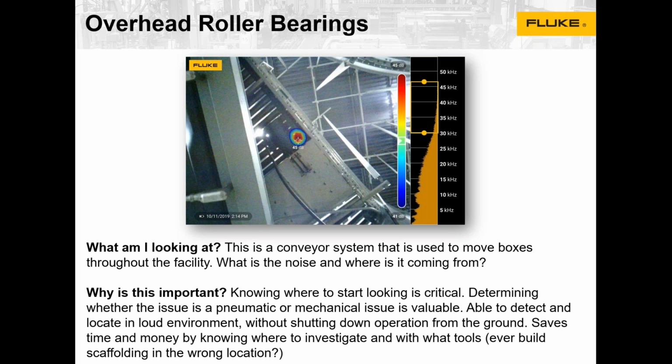And in this case, what we're looking at is actually noise from the bearing, but it could be a pneumatic leak as well. Being able to pinpoint that from the ground quickly can reduce your time and money in really getting up there and fixing it, bringing the right tools, even whether you're going to build scaffolding in a certain area or not. And so there can be a lot of money spent on scaffolding. I mean, some places spend millions of dollars just on scaffolding, and it's a value you might not think of right away. Adam, I don't know if you know this one as well, or if you have any other comments on it.